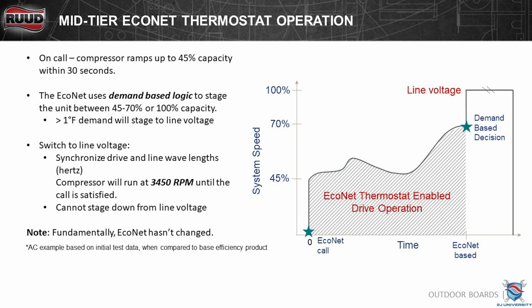So on the mid-tier, I want to explain how it works with an EcoNet and how it works in a 24 volt mode. Okay. On an EcoNet, it gets a call for cooling or heating, depending on whether it's AC or heat pump. It's going to go up to 45%. It will modulate between 45 and 70 as needed. It just goes up and down, full modulating. Once it hits that 70%, then you get the contactor snapping in, you get inrush voltage, and then it'll go to 100%. That is why it's important that you never push in the contactor on these. Because that inverter, as it's modulating, may only be at 180 volts or 130 volts, depending where it's at. Okay? Because it's running off that inverter drive.